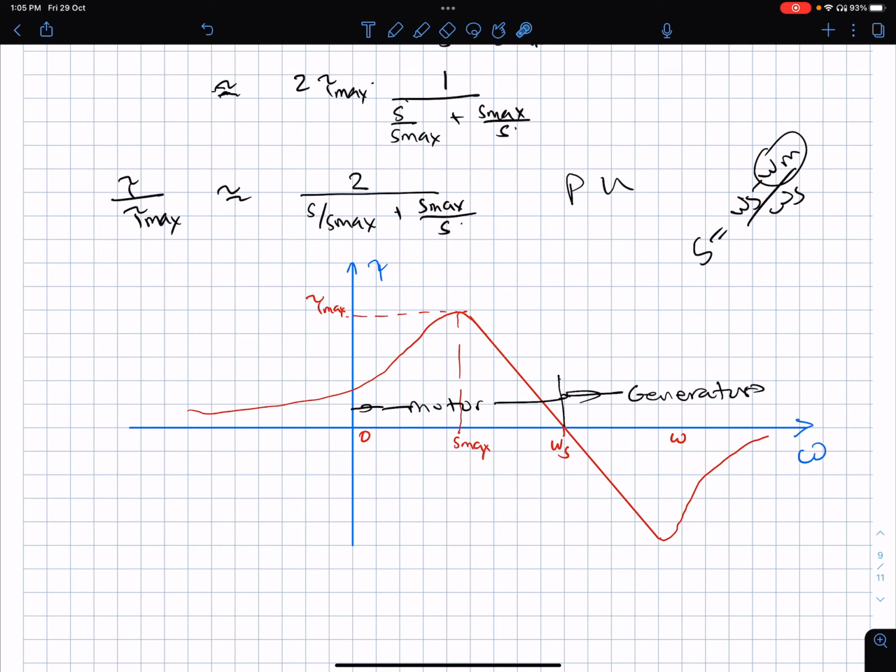That means suppose you are going down the hill with an electrical vehicle based upon an induction machine, for example a railway train coming down a ghat section, down the incline. What you do is flip the phases and create the rotating MMF in the direction opposite to the actual rotation going downhill.